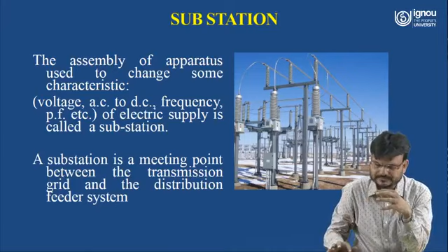So a substation is a meeting point between the transmission grid and the distribution feeder system. Typically, a substation consists of high and low voltage buses for power flow, and circuit breakers at transmission and distribution level. As I already told you, different types of circuit breakers may be used depending on how much voltage is used at that substation - like vacuum circuit breakers or SF6 circuit breakers. There are also other instruments used at substations, called metering equipment, and the control house, where relaying, measurement and control equipment are located.